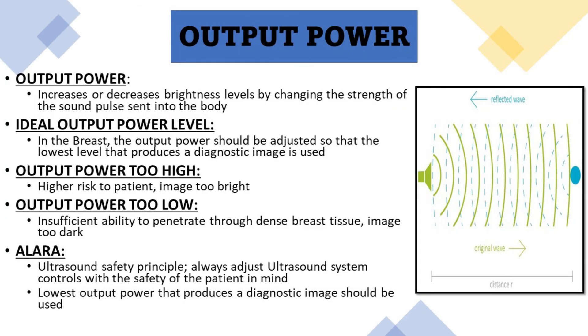The third brightness control is output power. Output power increases or decreases brightness levels by changing the strength of the sound pulse that's sent into the body. In the breast, output power should be adjusted so that the lowest level that produces a diagnostic image is used. When output power is too high, there's a higher risk to the patient and the image becomes too bright. When output power is too low, there's insufficient ability to penetrate through dense breast tissue, making the image too dark.